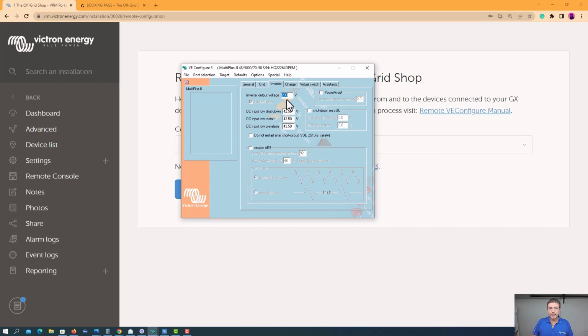And this is where you put your settings to turn your inverter on and off. Give you an example, the reason you use this, some batteries have a minimum voltage where the battery circuit breakers trip. So what you want to do, instead of your batteries tripping because they can't turn back on, you have your inverter turn off before it gets to that low point in your battery. So it just really depends on what battery and what system you've got.